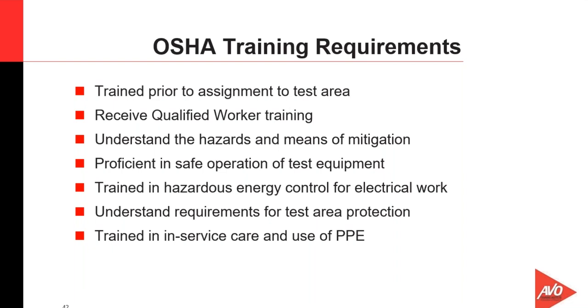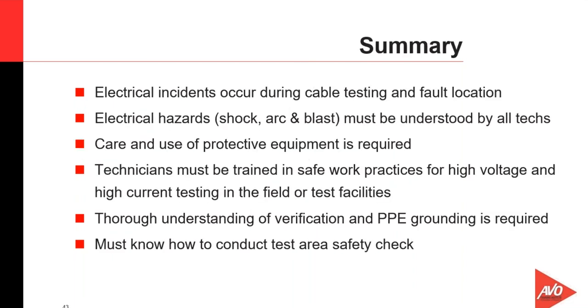Okay, we've covered a lot of ground, and a lot of this is oriented toward cable and fault locating and testing in the field, but it applies to overall high voltage and high current testing regardless of where the tests are being performed. Electrical incidents do occur. They do occur in cable testing.